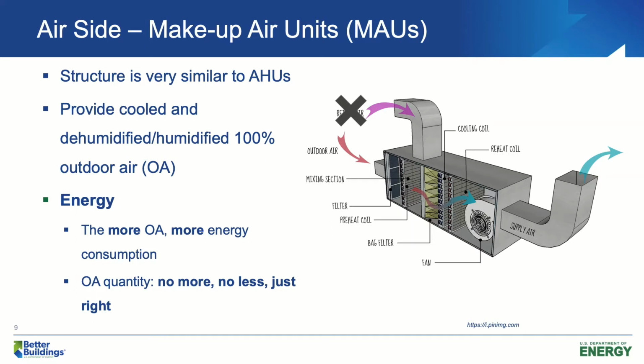Apparently, if we take more outdoor air, we will need more energy to cool and dry the air. Very similar to air cleaning. We do not want to under-ventilate our spaces because it might compromise the quality of our products and the health of our workers. But on the other hand, we do not want to over-ventilate our spaces either because it could mean energy penalty. You might wonder how much the energy penalty is for more outdoor air.